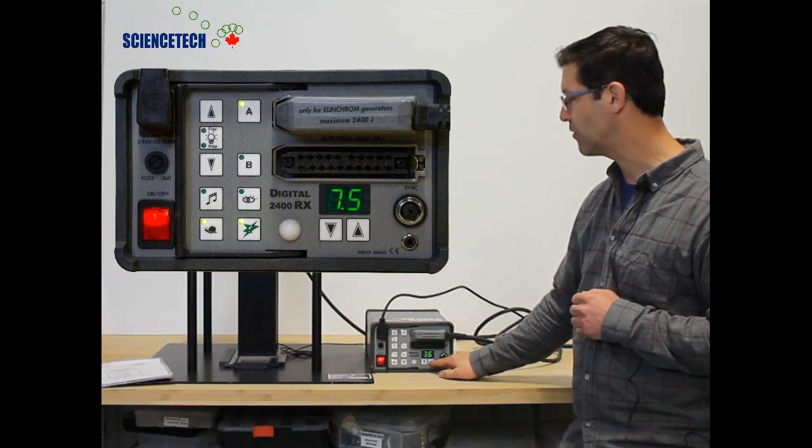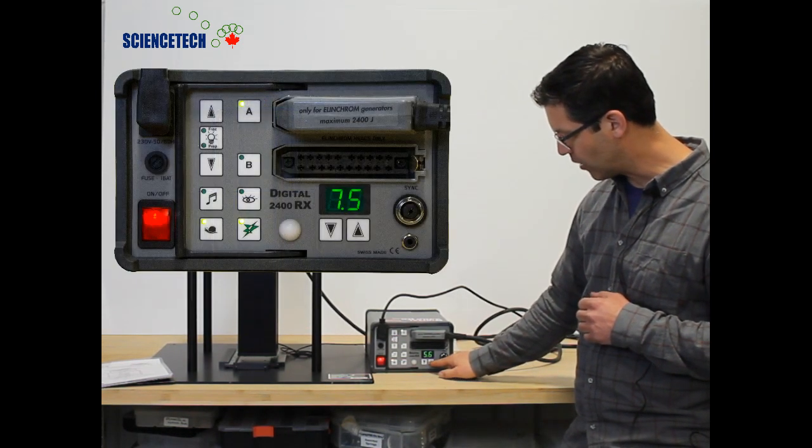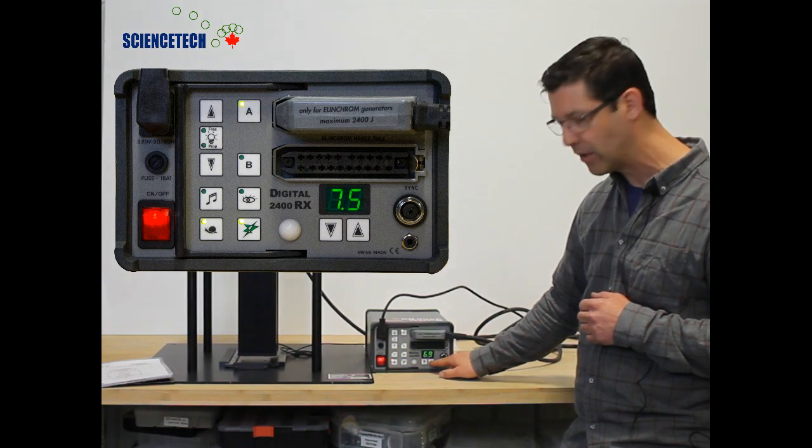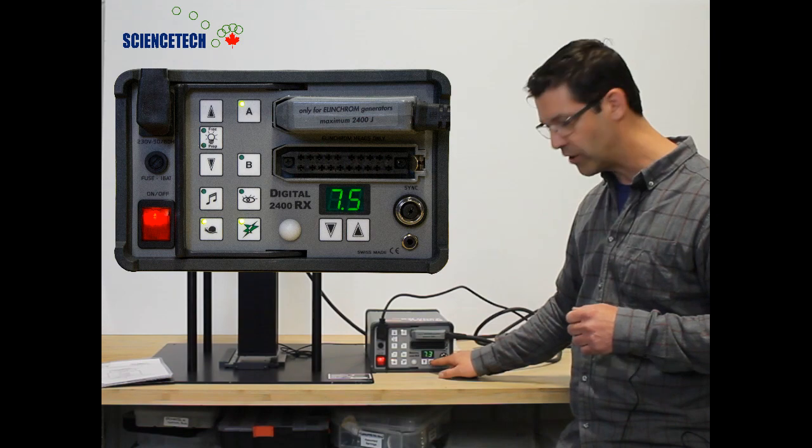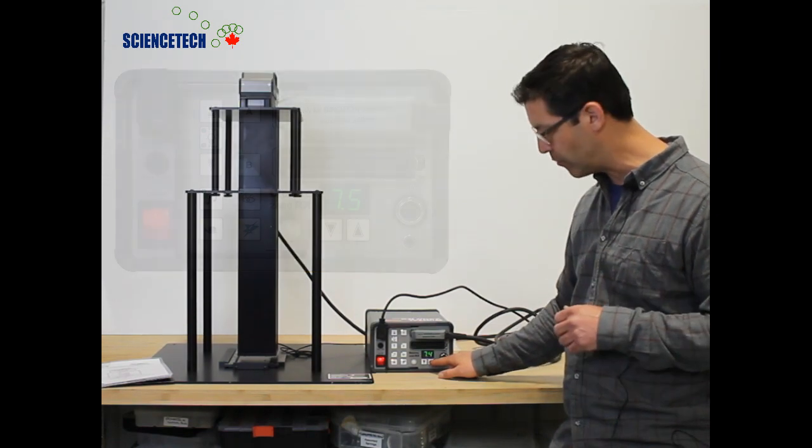I'm now going to increase to the maximum level allowed by the concentrator, which is 7.5. You should never flash past 7.5 on the supply. You should never flash at any number higher than 7.5.